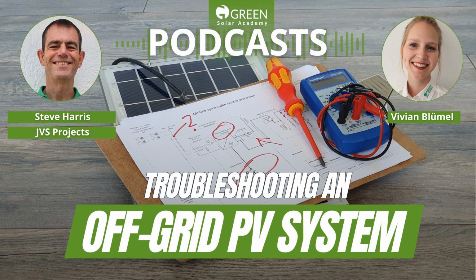So if you've got to a stage now where your inverter is running and it all seems well and everything's switched on, you've now got to say to the client, or you've got to do it yourself, what sort of loads does this inverter take? Do you put kettles on it or anything, and try and abuse it to reproduce a fault, and put a load on, put all the lights on, put the pumps on that you're using, the booster pump or the borehole pump or the sterilizer in the case of the clinics, and try and reproduce it. So you're basically just asking your client, okay, when did it appear first? And then you try to make everything as it was in that situation so that you try to make it trip again or fail again. That is a great way to try and visualize what's happening.